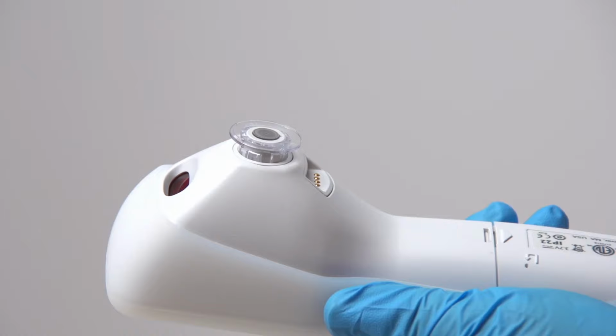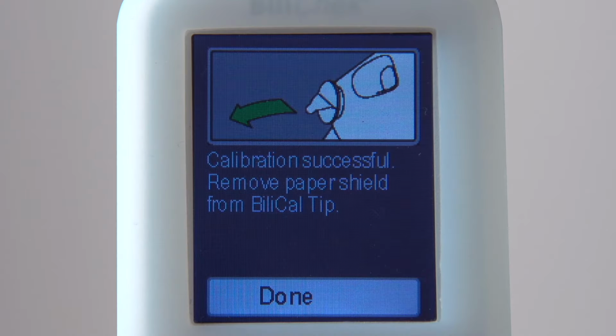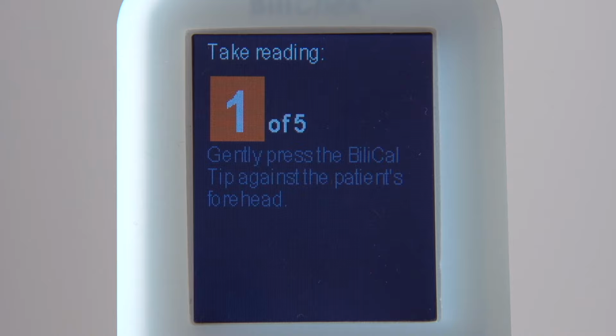To take a measurement, pull on the BiliCal tab and peel away the protective covering and calibration material from the tip and dispose of it. Leave only the clear film on the BiliCal tip. Press the Enter key to select Done. Gently press the BiliCal tip to the selected measurement area.